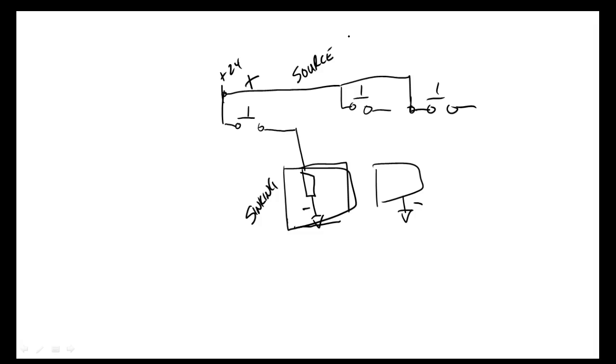So these Siemens PLCs over here, those inputs are sinking inputs. So that means my switch has to be hooked up to power, right? You understand? So my plus, that's one thing you got to know about the PLC. Some PLCs, you can change that. These Siemens PLCs, you can't.